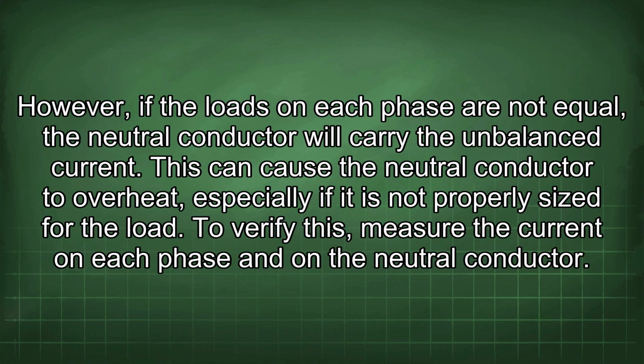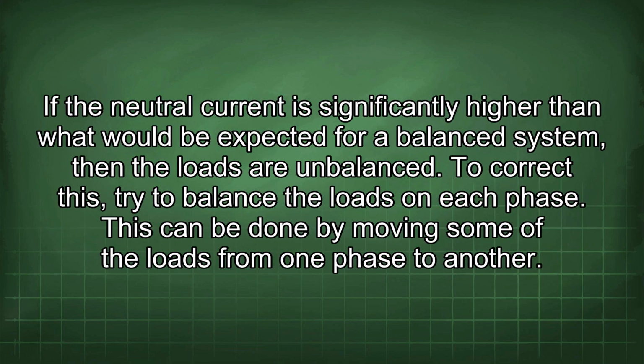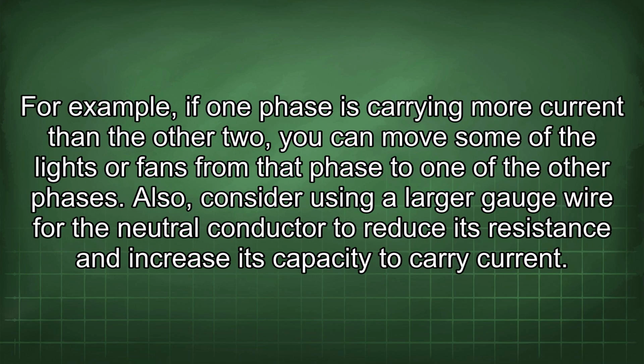However, if the loads on each phase are not equal, the neutral conductor will carry the unbalanced current. This can cause the neutral conductor to overheat, especially if it is not properly sized for the load. To verify this, measure the current on each phase and on the neutral conductor. If the neutral current is significantly higher than what would be expected for a balanced system, then the loads are unbalanced. To correct this, try to balance the loads on each phase. This can be done by moving some of the loads from one phase to another. For example, if one phase is carrying more current than the other two, you can move some of the lights or fans from that phase to one of the other phases.